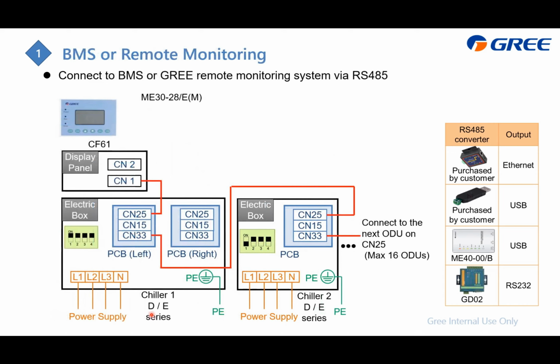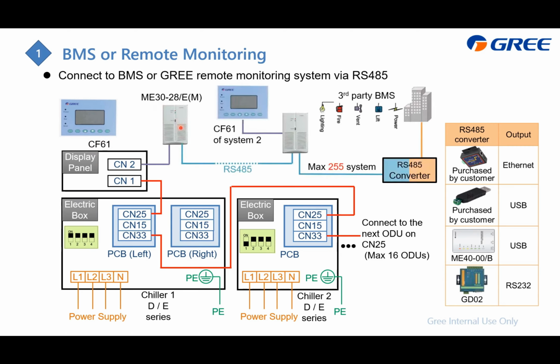Also for the on-off, we have another controller, which is this one, CF61. The wiring is also similar, which means from the first CN33 to the next CN25, and you also need to change this switch. From here, you also need to connect it to the BMS system. But before that, for this CF61, we need an ME30, which is this one, as we need to change the output to the RS485 signal.